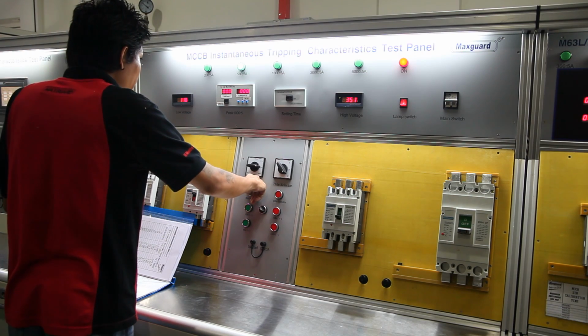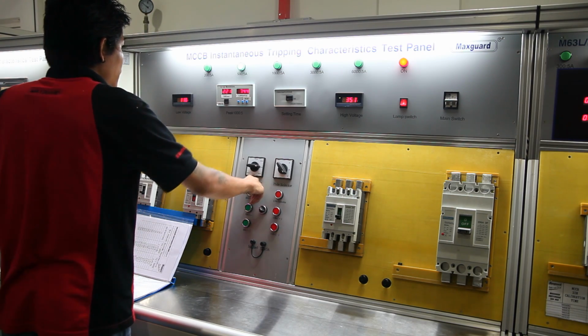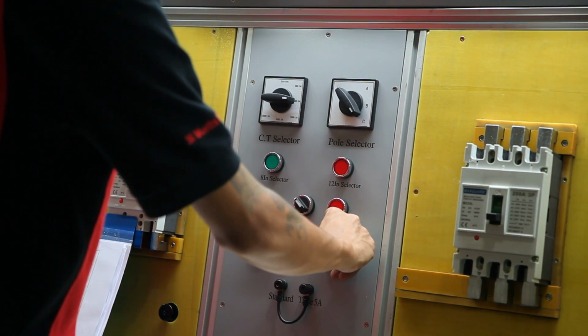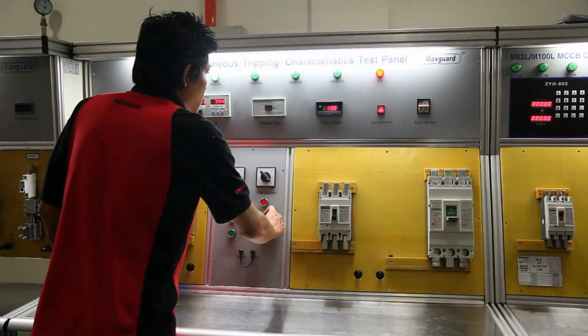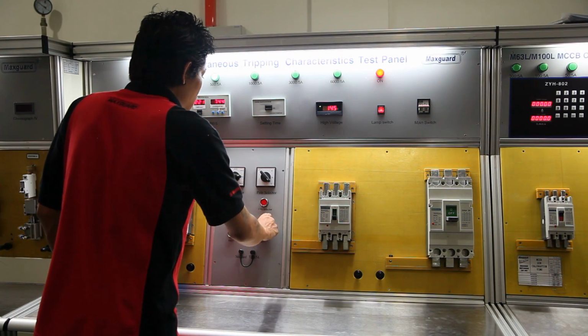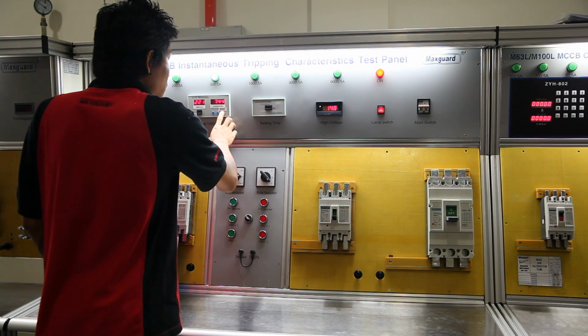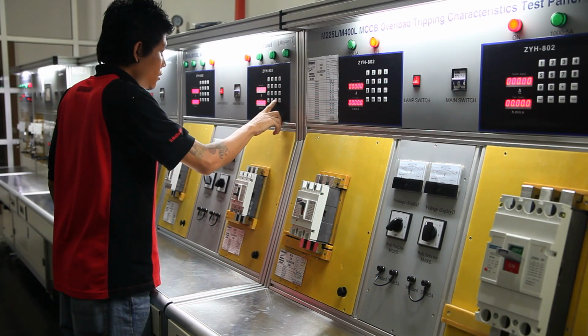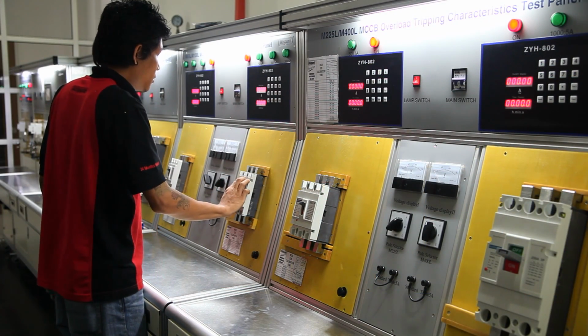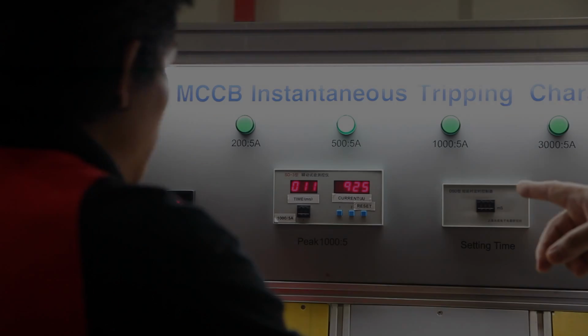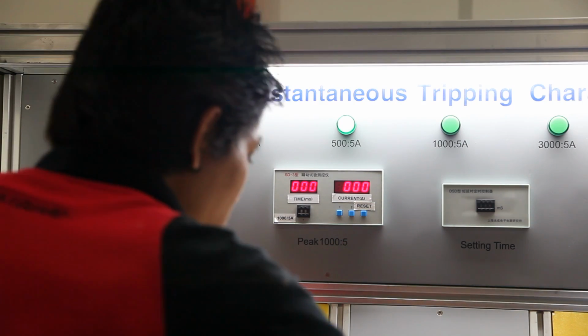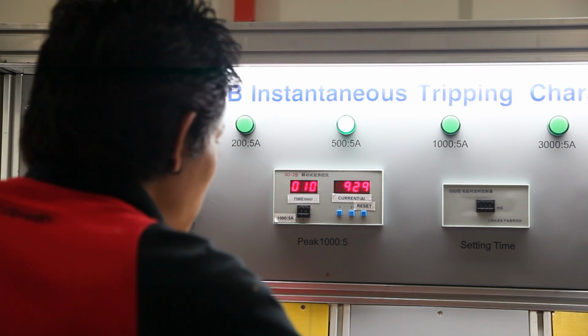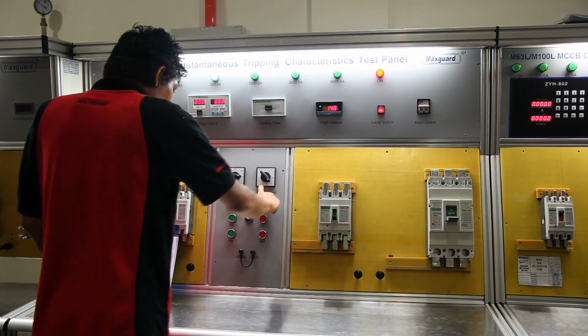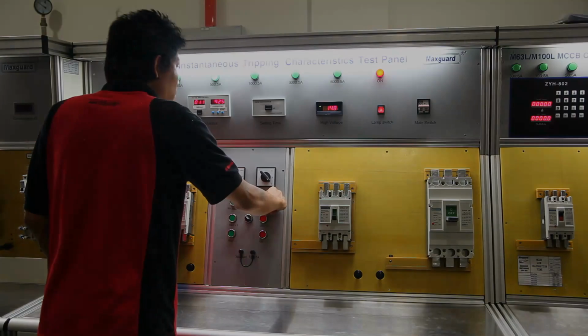Instantaneous tripping test for MCCBs. The instantaneous non-trip time and trip time is above 0.2 second at 8 times current and below 0.2 second at 12 times current respectively. This test is to prove the response of the MCCB to surge current. Testing is conducted pole by pole.